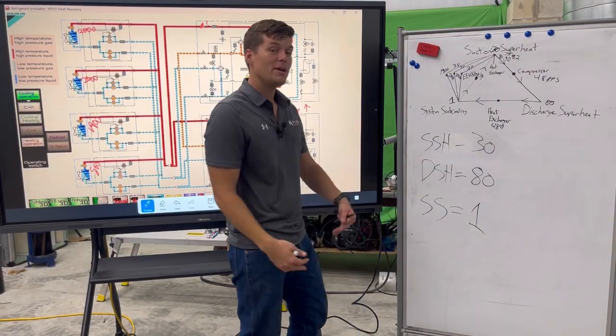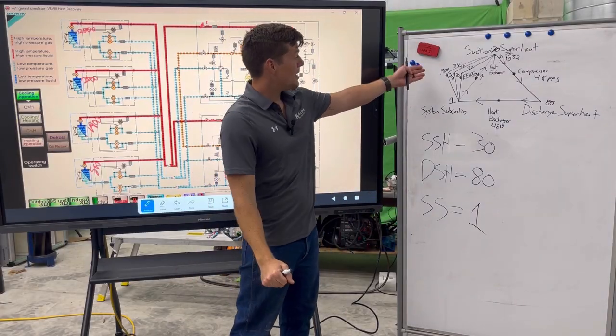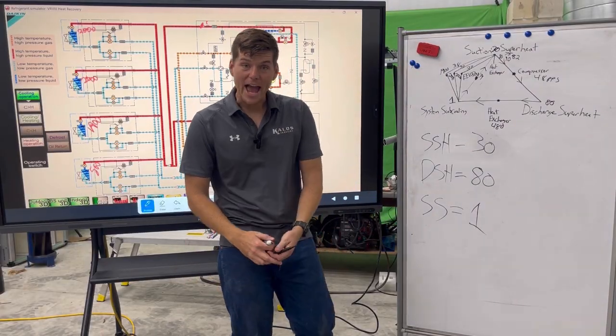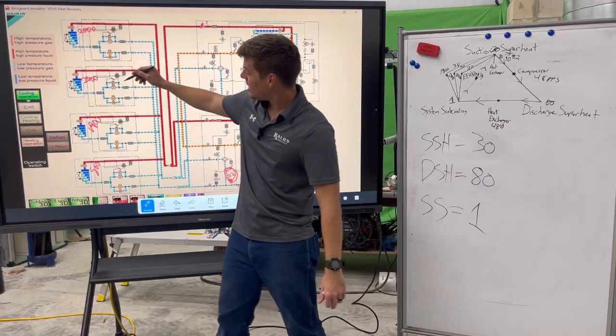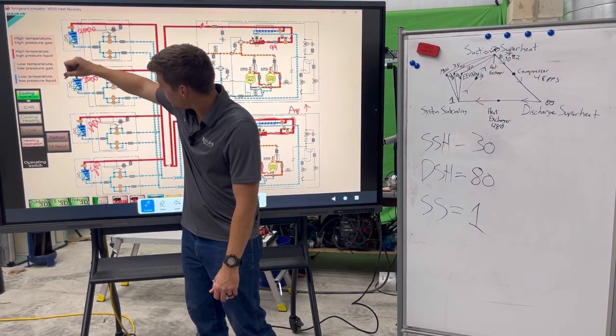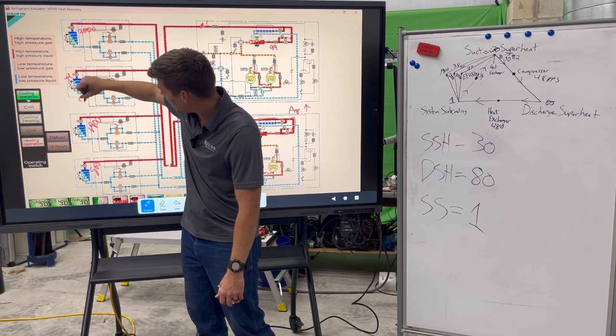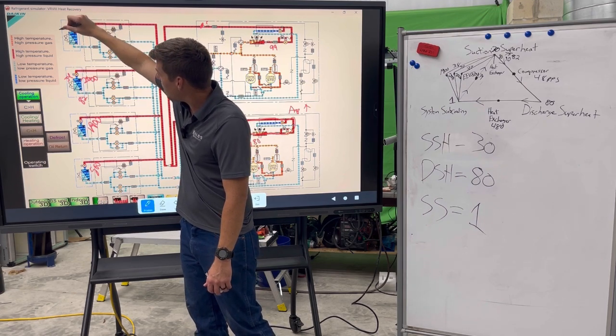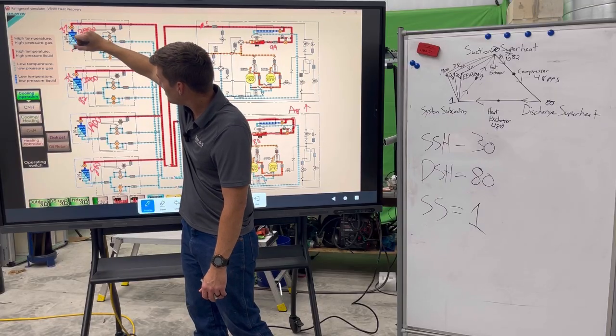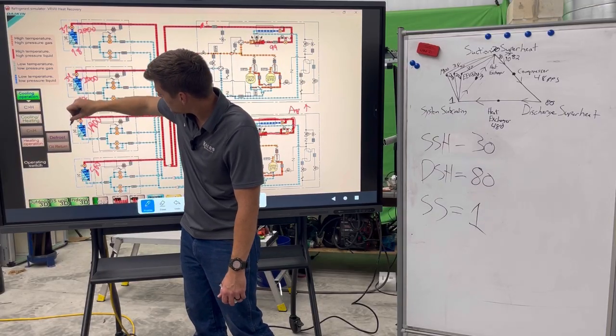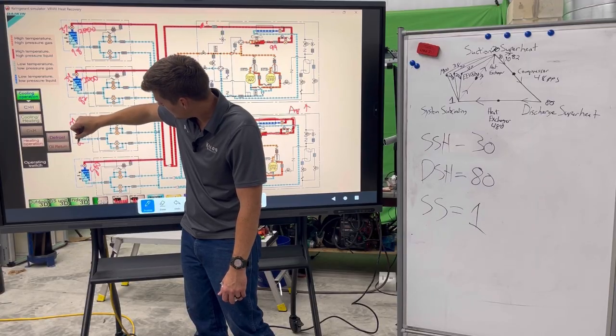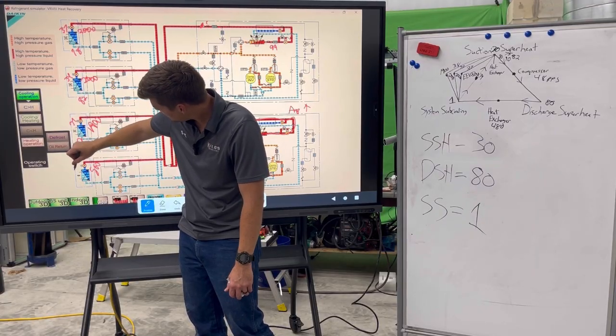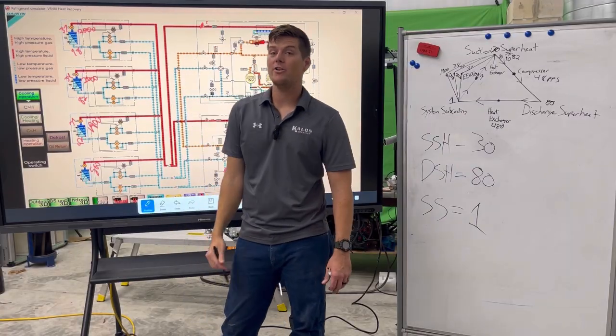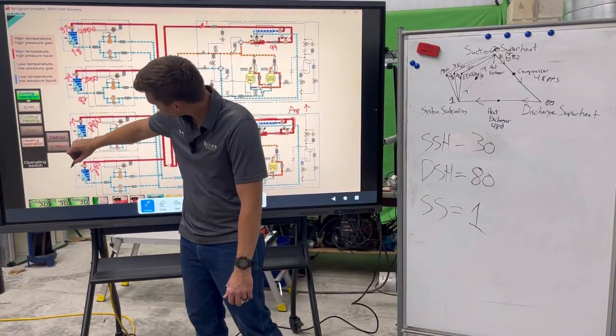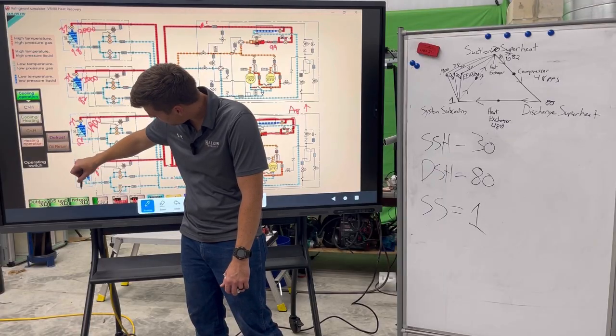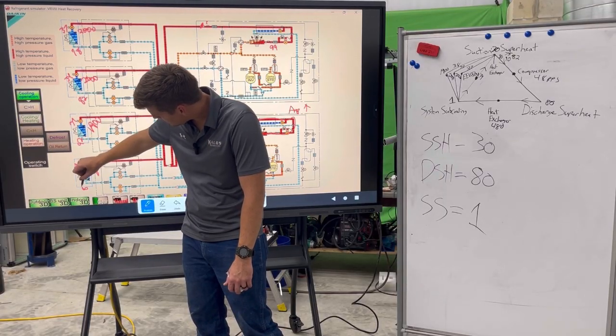Well, again, it's not metering refrigerant because the valves are wide open, and my superheat across all my indoor coils is trash. It's garbage, coming in and going out. And again, what does that look like? So over here, we marked it, 34 degrees. Out the other side, it's 82 degrees. Coming into my valve, it's 37 degrees. Coming out is 78 degrees. Over here is 37 degrees. Coming out is 92 degrees. Well, that is a really hot space. Again, your suction temp is going to be matched by your ambient in that space, so maybe it is really hot in that room. And then last but not least, 34, and coming out the other side, let's say this is 82.